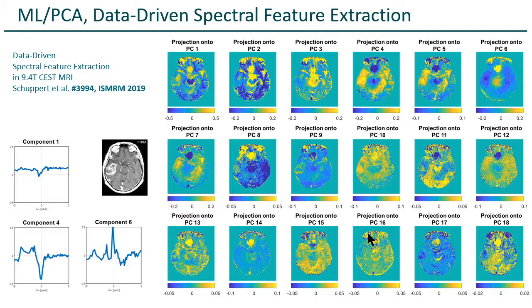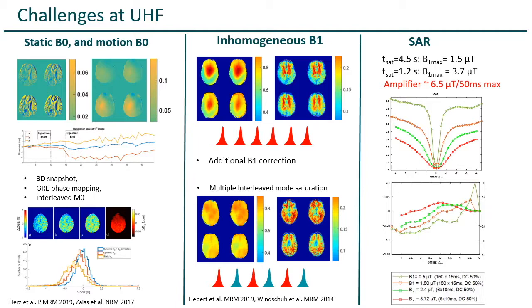Of course, we have a lot of challenges. You have to take care of B0 and motion-induced B0 changes. Motion is a big issue, so we try to solve that with 3D snapshot and co-registration. B1 is very inhomogeneous, and you have to do B1 correction or use parallel transmit methods to mitigate that. SAR can also be a big issue at 9.4T — sometimes if you have a protocol at 3T, you cannot directly translate it to 7T or 9.4T because it's too much SAR. However, going to lower power sometimes has benefits.